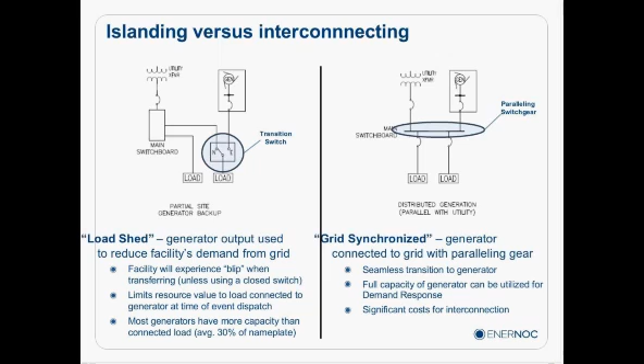Facilities can also interconnect, either briefly or for a longer duration, meaning the generator is connected to the grid directly. That provides a seamless transition and allows the full capacity of the generator to be used. It does cost more to have a closed transition switch installed, partly due to permitting, because a facility that participates interconnected often requires a more rigorous air permit than one that is just islanded. We find the vast majority of customers do island; very few are grid synchronized.